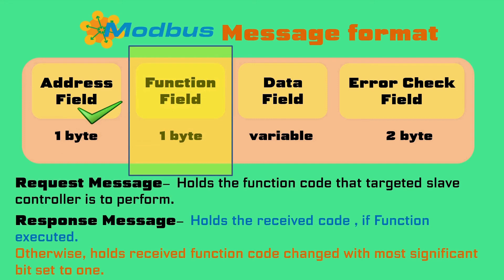The second field is the function field, which also offers a single byte of information. In request frames, this byte identifies the function that the targeted slave controller is to perform. In response frames, if the targeted slave controller was able to perform the requested function, the same function code will be sent back. Otherwise, the function field of the request will be echoed with its most significant bit set to 1, thus raising an exception in the response frame.